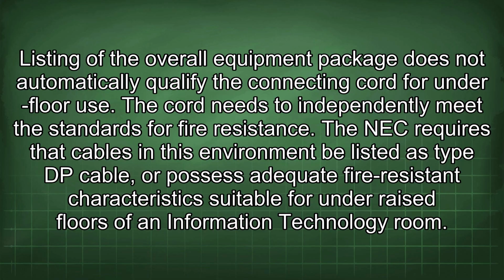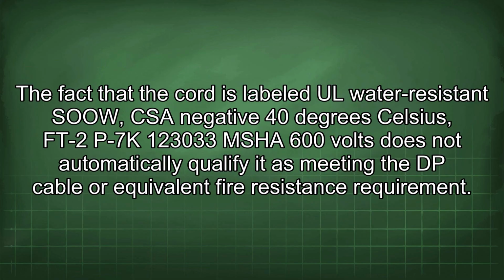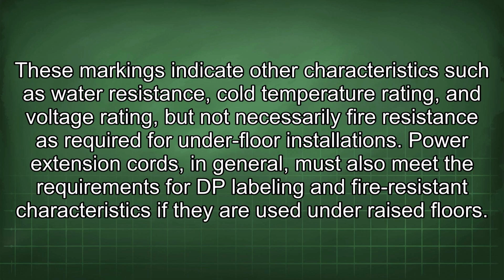The NEC requires that cables in this environment be listed as Type DP cable, or possess adequate fire-resistant characteristics suitable for under-raised floors of an information technology room. The fact that the cord is labeled UL water-resistant SOOW, CSA negative 40 degrees Celsius, FT-2P-7K 123,033 MSHA 600 volts does not automatically qualify it as meeting the DP cable or equivalent fire resistance requirement. These markings indicate other characteristics such as water resistance, cold temperature rating, and voltage rating, but not necessarily fire resistance as required for underfloor installations.